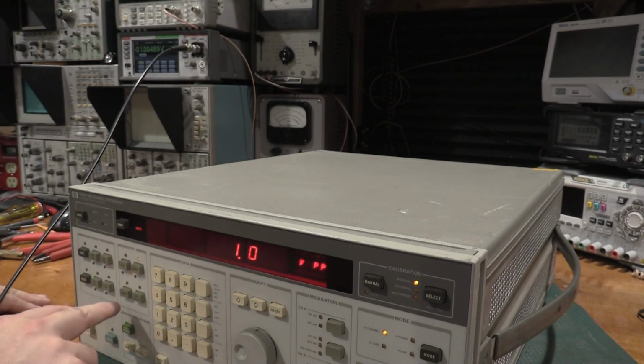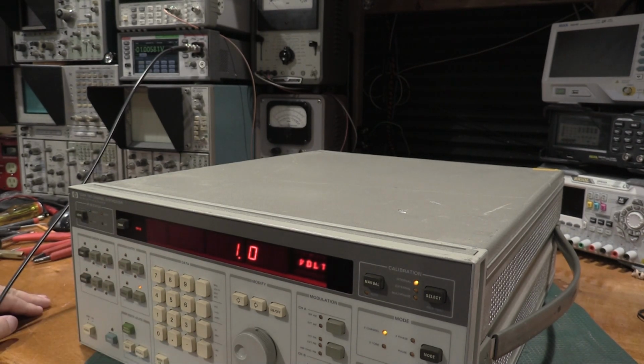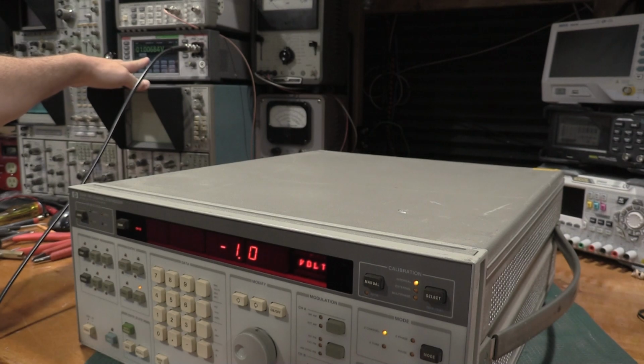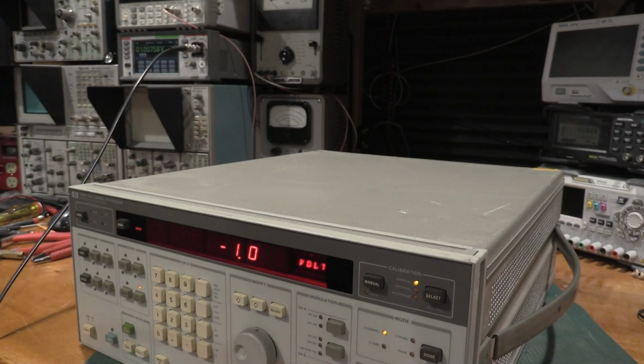Same setup, 1 kilohertz, 1 volt peak to peak with a 1 volt DC offset. And if I do a negative 1 volt DC offset, it'll kick over negative and it'll be at accuracy. It's plus or minus 75 millivolts. So the unit is actually calibrating and aligning exactly the way it's supposed to.